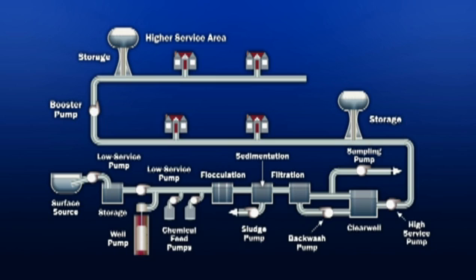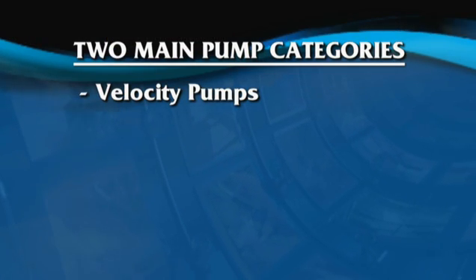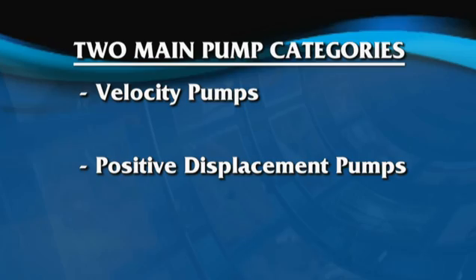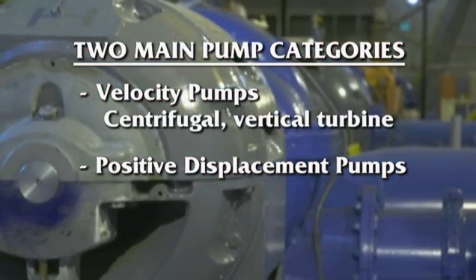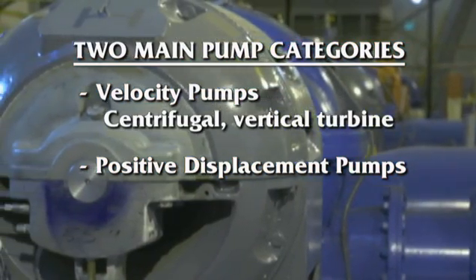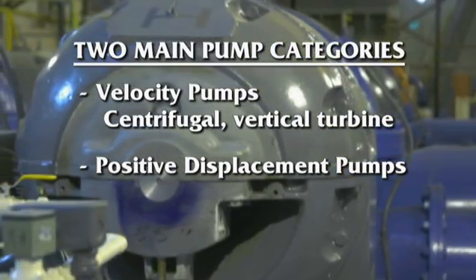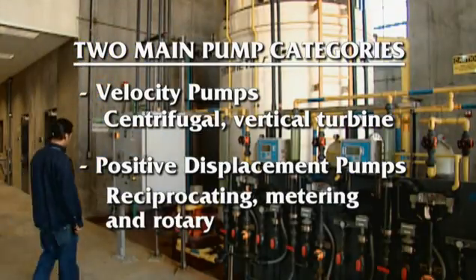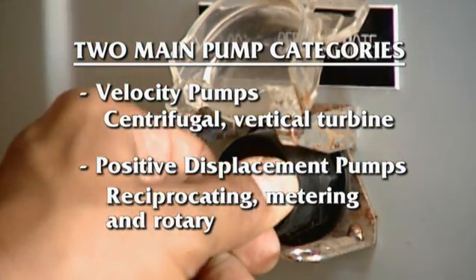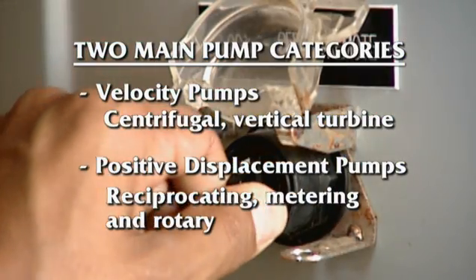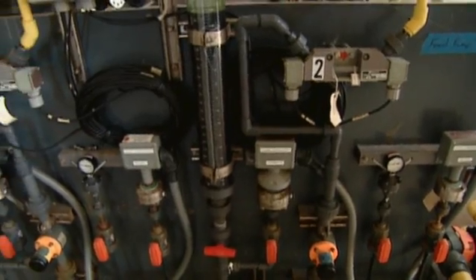The two main categories of pumps used in water supply are velocity pumps and positive displacement pumps. Velocity pumps, including centrifugal and vertical turbine, are used for most distribution system applications. Positive displacement pumps include reciprocating and rotary, and are used for moving abrasive or harmful materials and metering chemical feed systems.